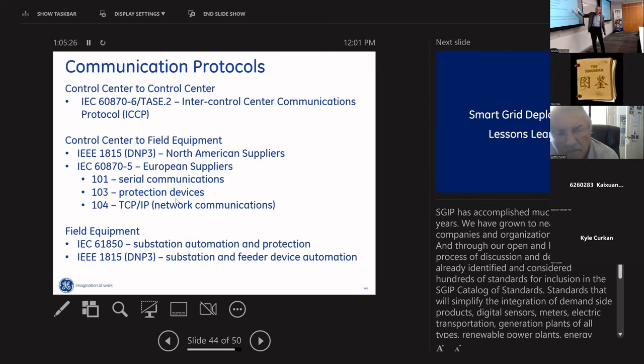Now, from control center to field, there are 2 protocols. In North America, we've always used a lot of DNP3, Distributed Network Protocol 3, which is IEEE Standard 1815. European suppliers use IEC 60870-5, 101 for serial and 104 for network. Then when we're in the field, IEC 61850 is really the global standard, but again in North America we still use DNP3. It's very easy - we've converged on a very small number.